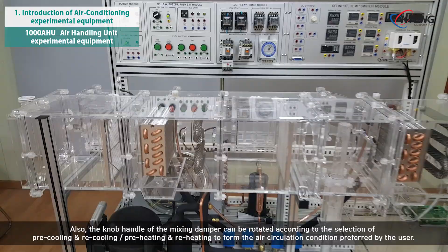When the switch on the main power module of the control panel is turned on, the AC lamp is lighted to supply the power to the temperature indicator, and the temperature value is indicated. Also, when the toggle switch on the 24-volt power unit is turned on, the DC lamp is lighted to finish the preparation for initiating the load test.